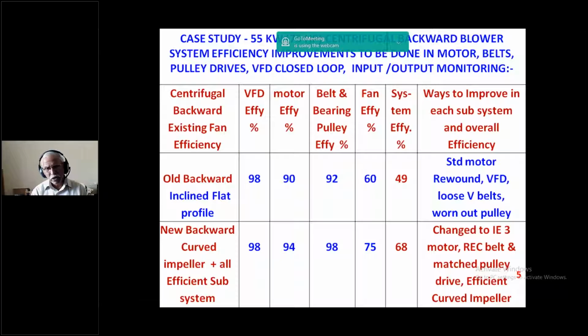Then comes the pulley, belt and bearing loss. It is maintained at 2% only instead of 8%. And the fan efficiency has gone from 60 to 75. Totally it's almost 70%, so a 20% jump in the efficiency of the given blower system. This is the area we wanted to concentrate on in the industry. Wherever replacement is needed on the existing inefficient subsystems, it has to be done, or a retrofit has to be done to achieve a better efficiency point in the fan performance curve.